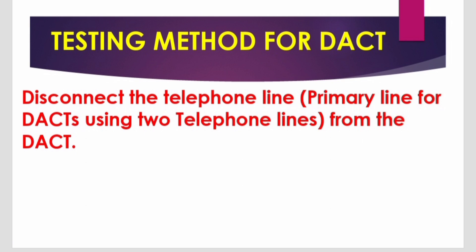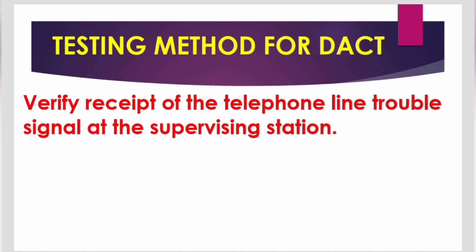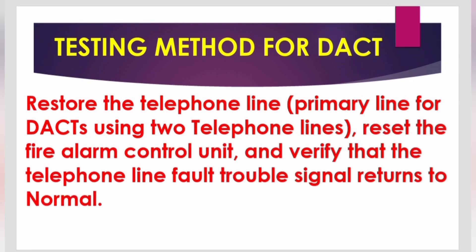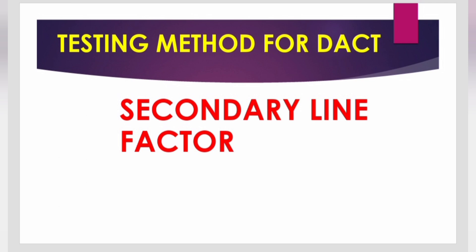For the primary line factor, disconnect the telephone line primary for the DACT. Using two telephone lines, verify the indication of the digital alarm communicator transmitter trouble signal occurs at the premises fire alarm control unit within four minutes of detection of the fault. Verify receipt of the telephone line trouble signal at the supervising station. Restore the telephone line, reset the fire alarm control unit, and verify that the supervising station receives the restoral signal from the communicator.